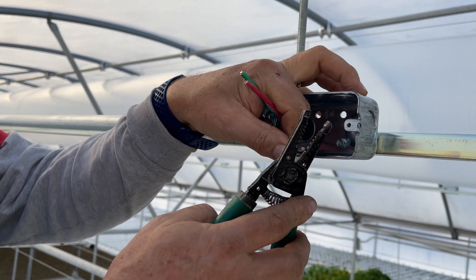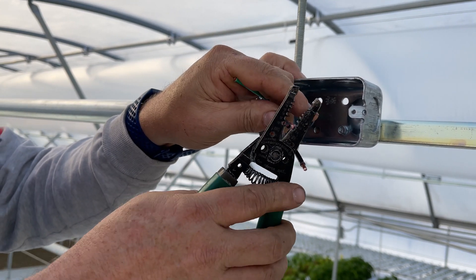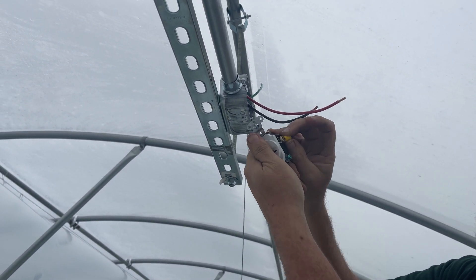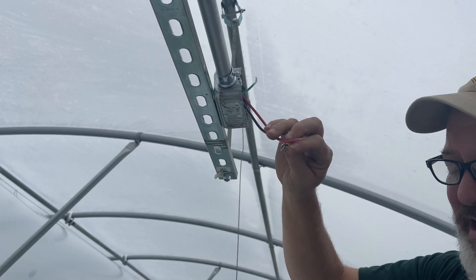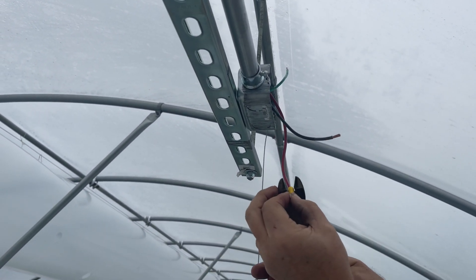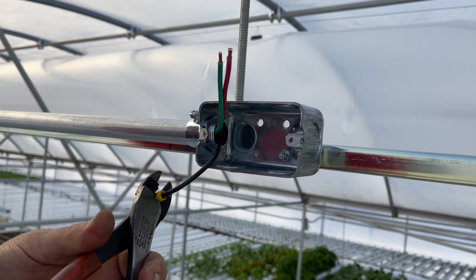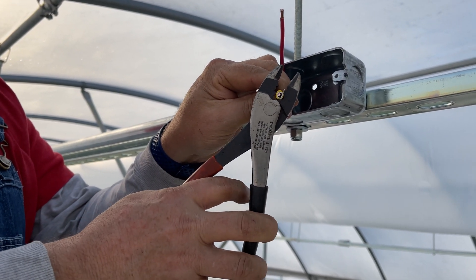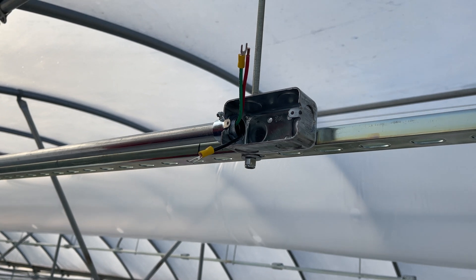Now that I have all the wires run in the conduit and they're all coming out of the box, we have to strip the insulation. We're going to use forked connectors to go into the outlets — that'll give us a better contact than trying to put bare wires around the screws. I never liked that and it's just not a good way to do it. These are really easy to install and they're made for 8 to 12 gauge wire. You need these special pliers which are easy to get. Put it in, crimp down on that fitting, and it will make a little indent right there.